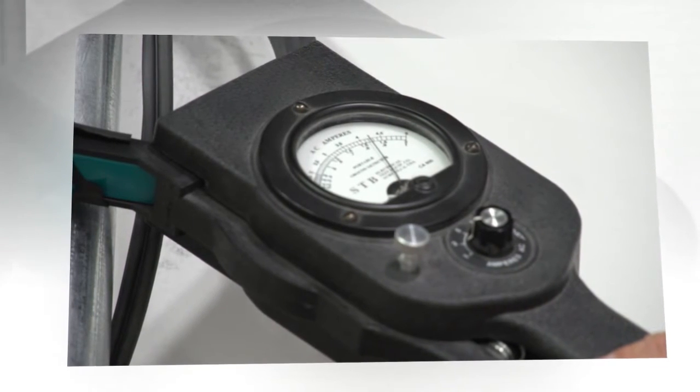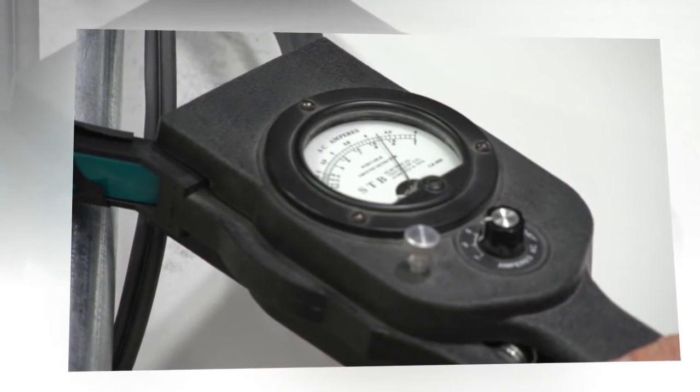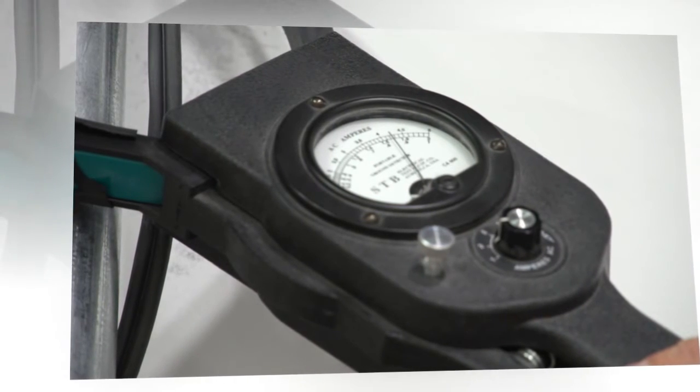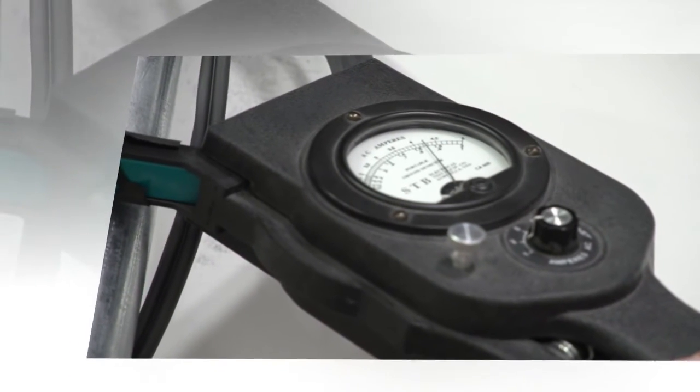If there's a ground fault, it could go through any other grounded path. So when that occurs, we see this current in this path, and now we know that the ground fault is in this path. And it makes it easier to track down the fault.